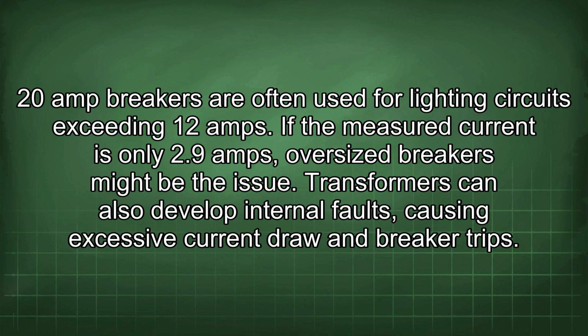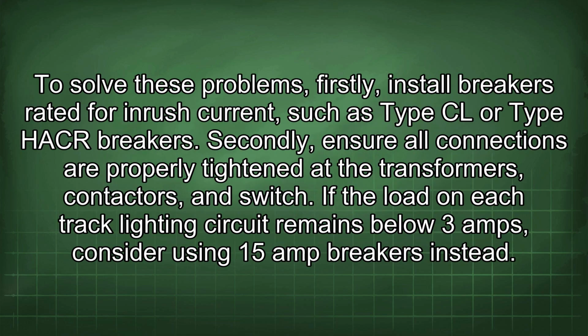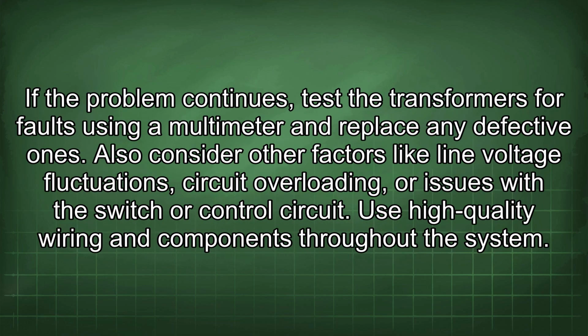Transformers can also develop internal faults, causing excessive current draw and breaker trips. To solve these problems, firstly, install breakers rated for inrush current, such as Type CL or Type HACR breakers. Secondly, ensure all connections are properly tightened at the transformers, contactors, and switch. If the load on each track lighting circuit remains below 3 amps, consider using 15 amp breakers instead. If the problem continues, test the transformers for faults using a multimeter and replace any defective ones.